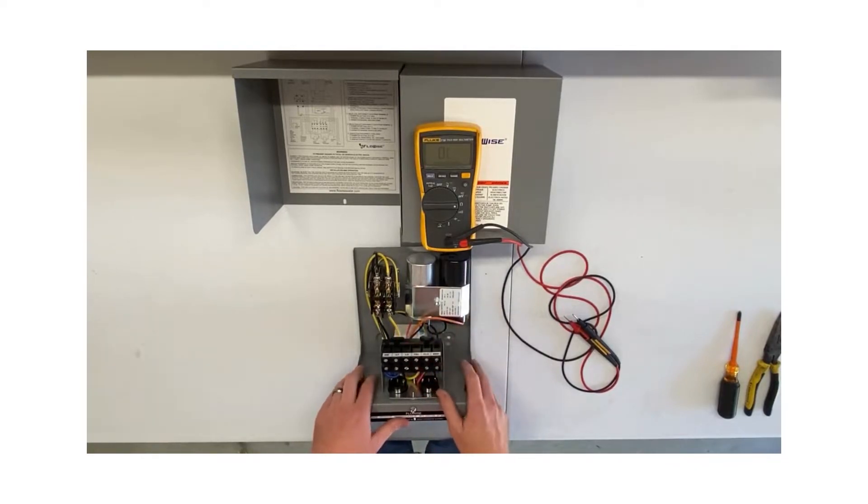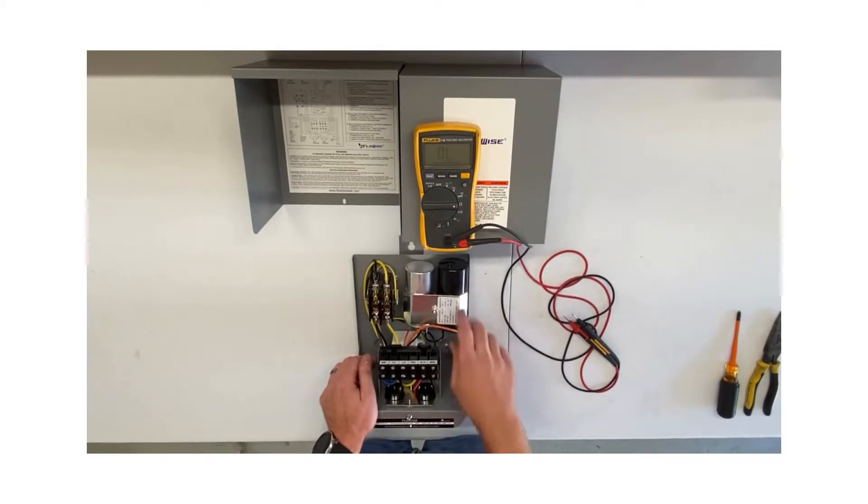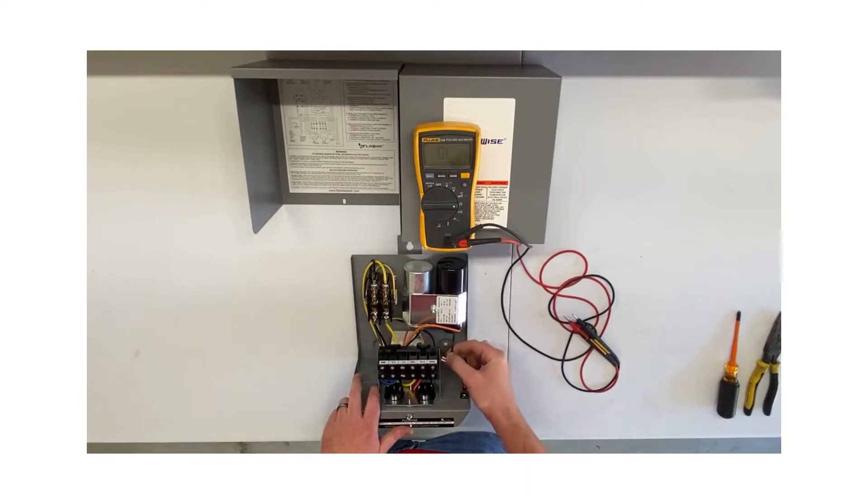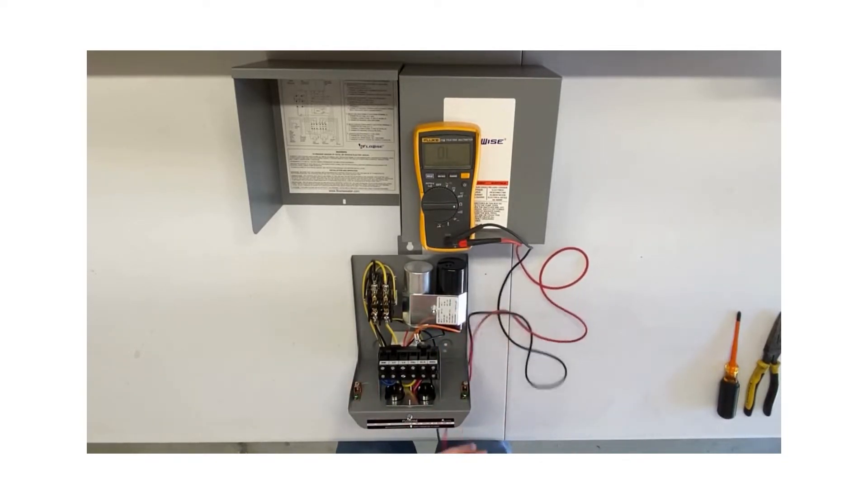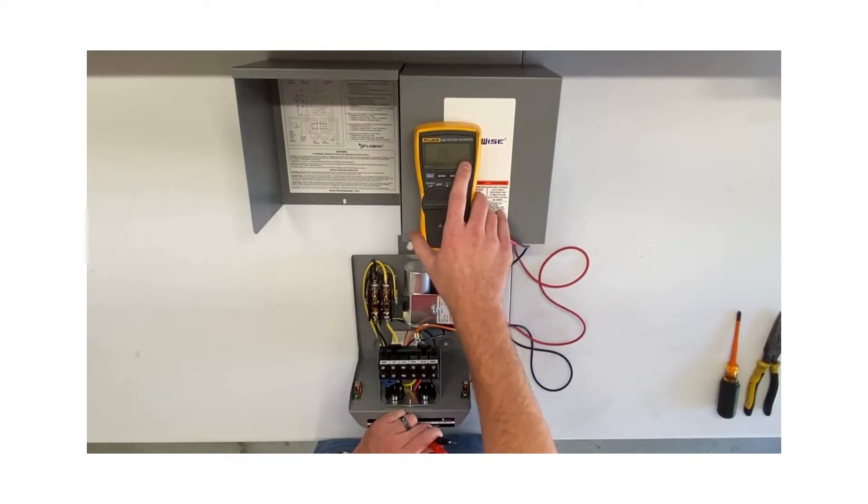This is probably one of the most common points of failure in the box—the capacitor. Our testing procedure is going to be the same for the start or run capacitor. The first thing you're going to do is remove one lead from each capacitor. A little trick is there's a wire that jumps between each capacitor, so if I remove it just from one side, that serves as removing a lead off of each capacitor.